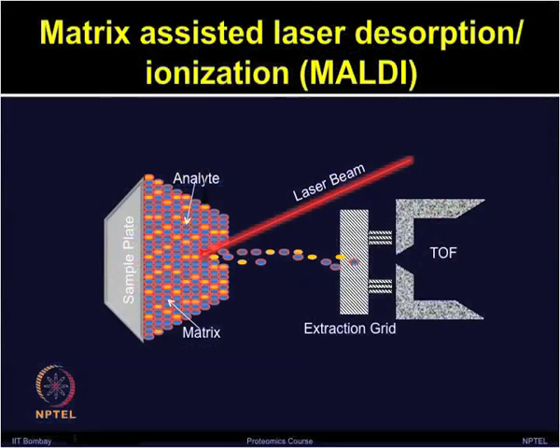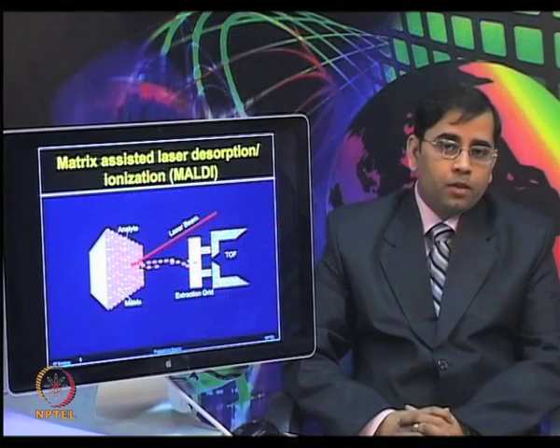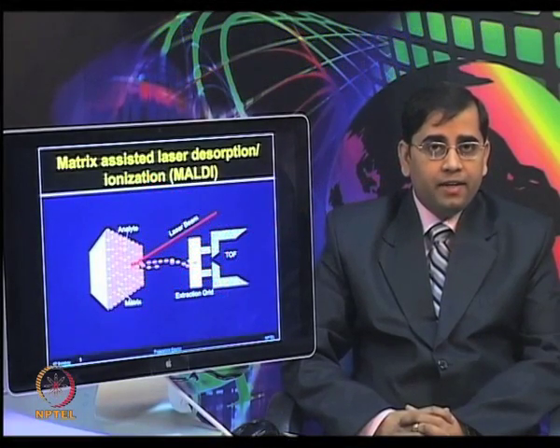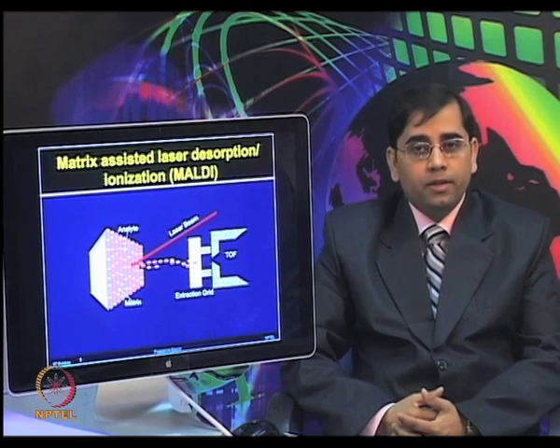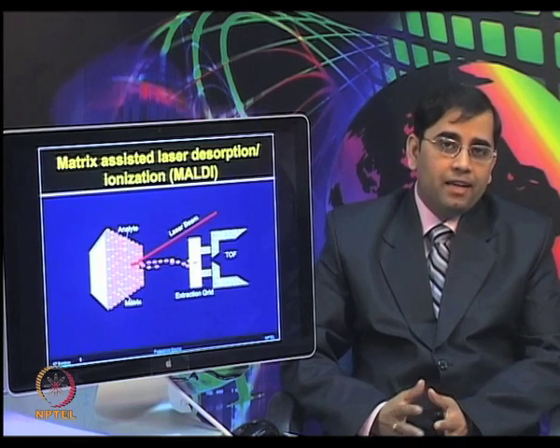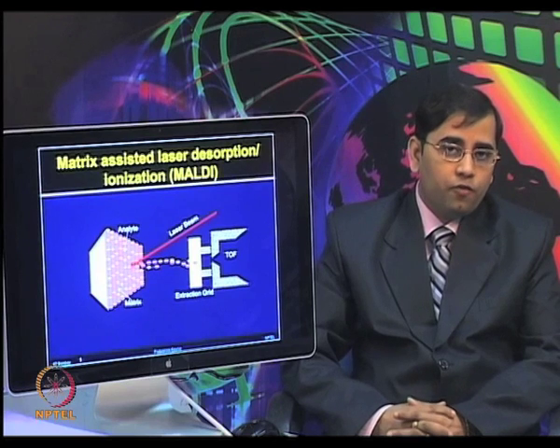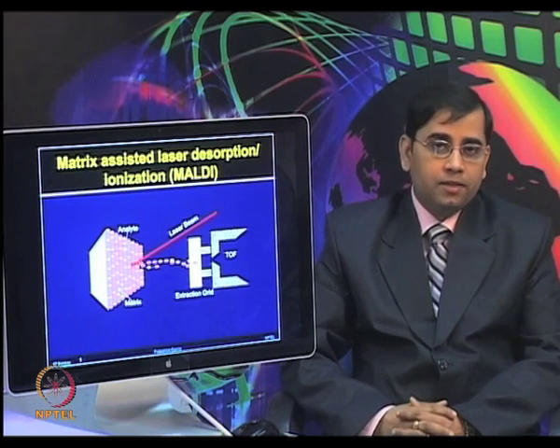Once the matrix and analyte are placed on the target plate, it is put in a vacuum chamber with high voltage applied. The crystals are targeted with short laser beams, and rapid sublimation converts the analyte into gas phase ions. These ions, once generated, accelerate away from the target plate through the mass analyzer — which is a time-of-flight (TOF) tube — and reach the detector.